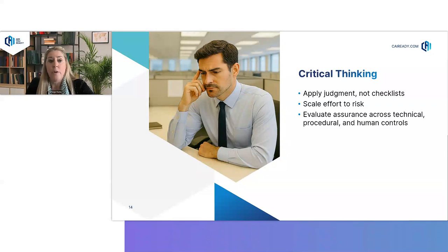So this helps us avoid verification where we always do a document called this, a document called this, and a document called that. That's not what we want. The critical thinking helps us think through the testing controls, the procedural controls, and the human performance elements that we need when we design our testing approach. And when teams consider this holistically, I think the verification becomes stronger. We can reduce our redundant testing and our timelines will shorten. And I think it puts us in a much better position for inspection readiness. So this mindset shift is very important to iterative C&Q in our real environments on the plant floor.